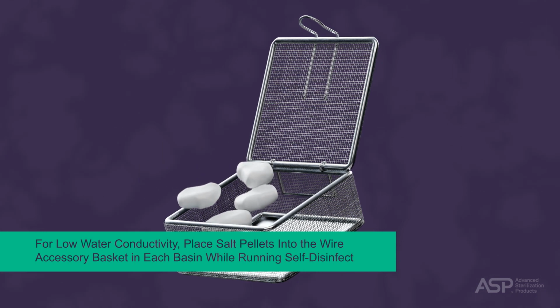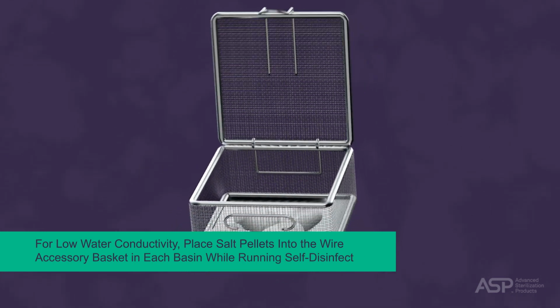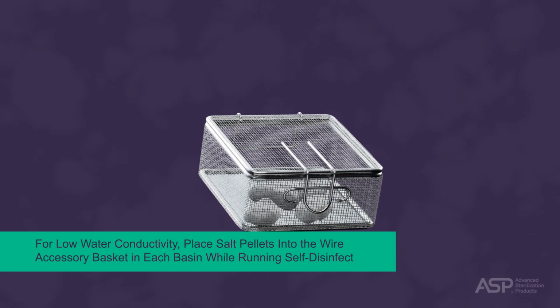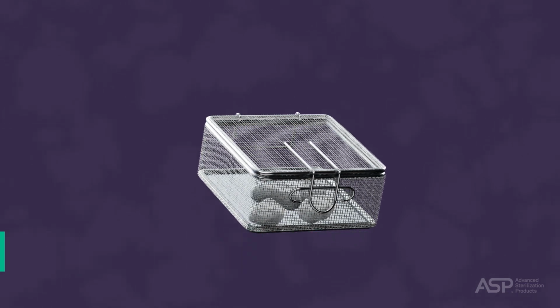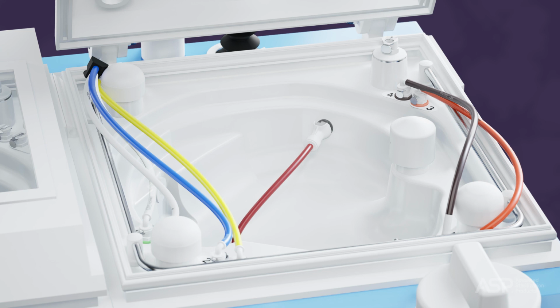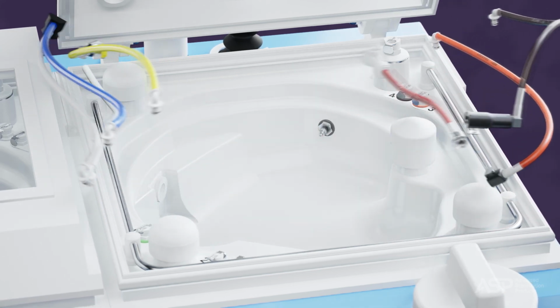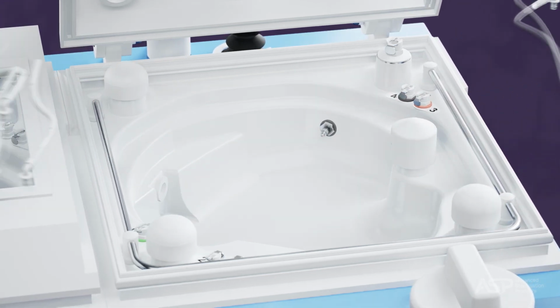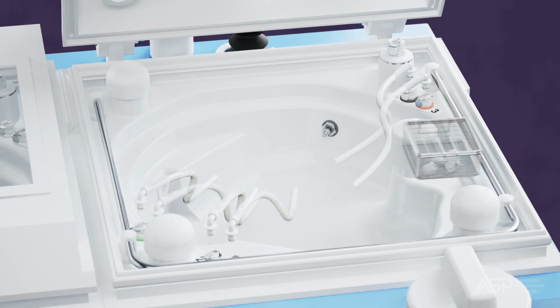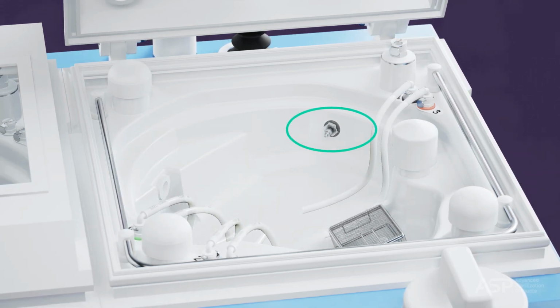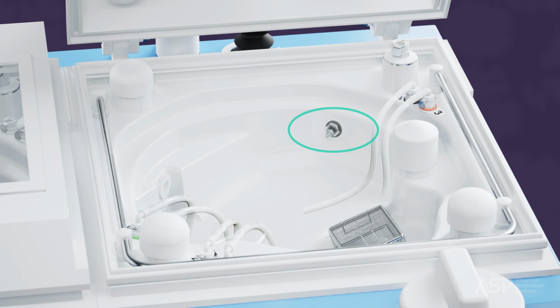If your facility is known to have low water conductivity, you may need to place salt pellets into the wire accessory basket in each basin while running a self-disinfect. To perform a self-disinfect, remove all endoscopes, accessories, and colored connectors. Replace the colored connectors with 6 clear connectors. The red leak connector should be removed, but not replaced with another connector.